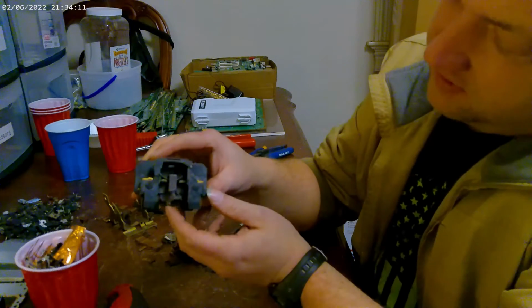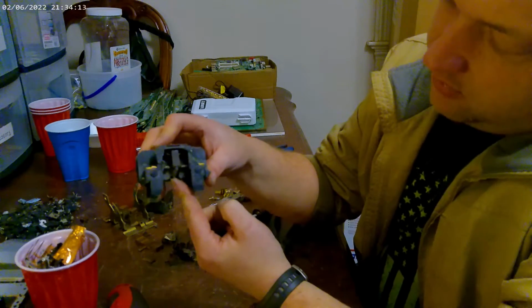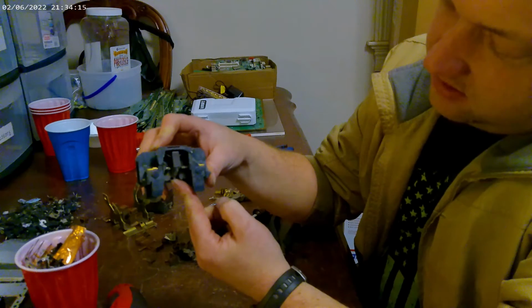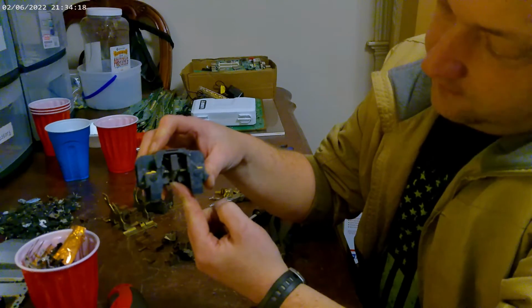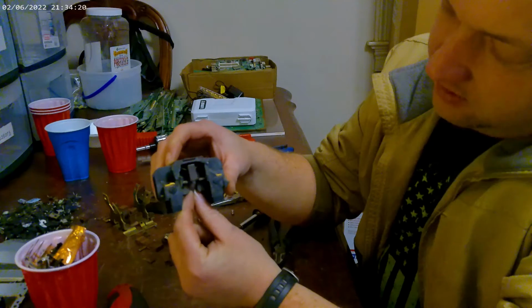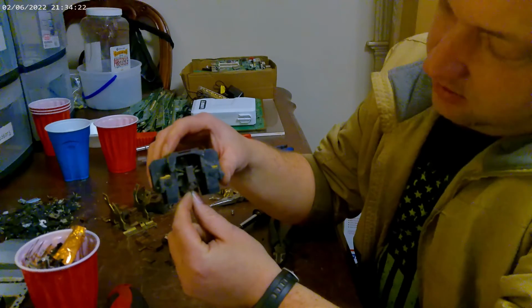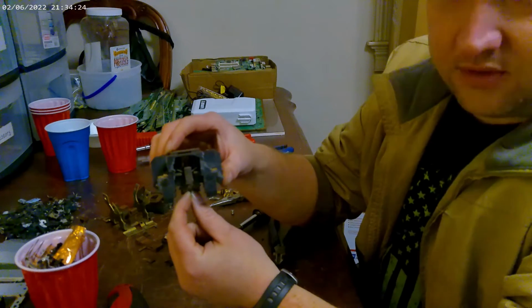So there it is, it's nice and open now. So that spring on the bottom stays open when that contactor turns on. The low voltage pulls a magnetic field. It grabs that metal and pulls it down, and it makes contact just like that with the other two.